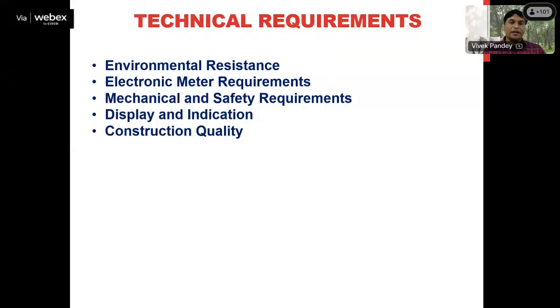Next, related to the display and indication unit, a clear, stable, and non-resettable display should be there. The indication should display the quantity of gas in SI units, that means cubic meters or kilogram. Cubic meter can be cubic decimeter or cubic centimeter. Cubic centimeter means milliliter, cubic decimeter means liters, and cubic meter means 1 kiloliter. So it can indicate the reading in kiloliters, cubic meters, or kilogram. Such a type of display should be there. And the electronic display must retain the last reading after a power interruption.